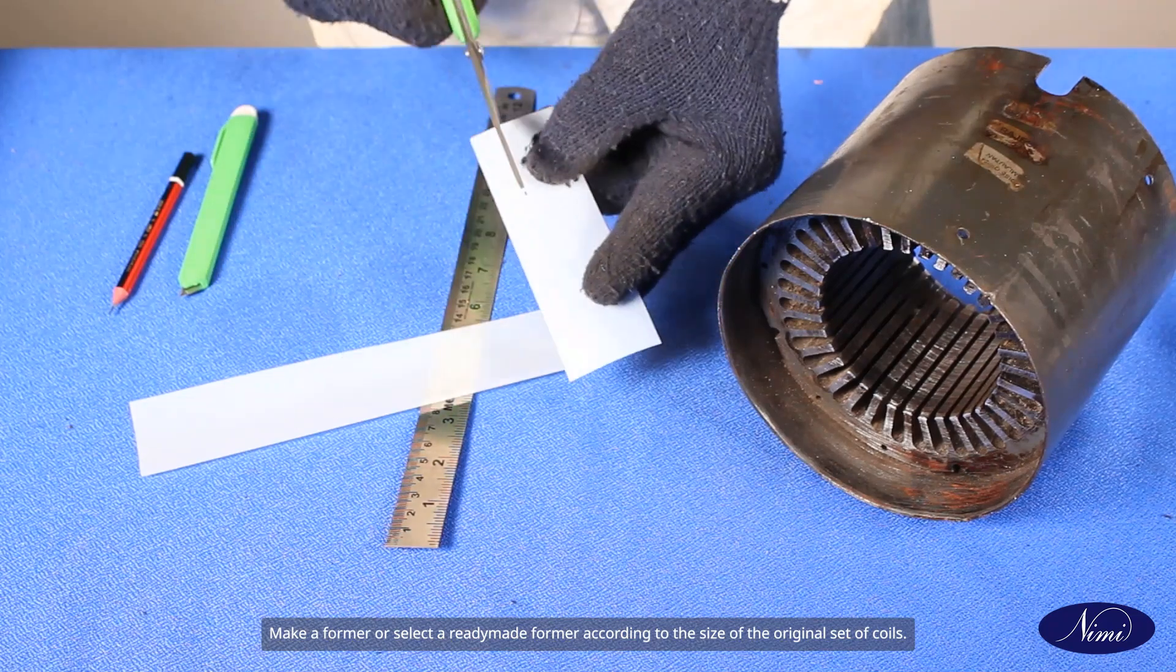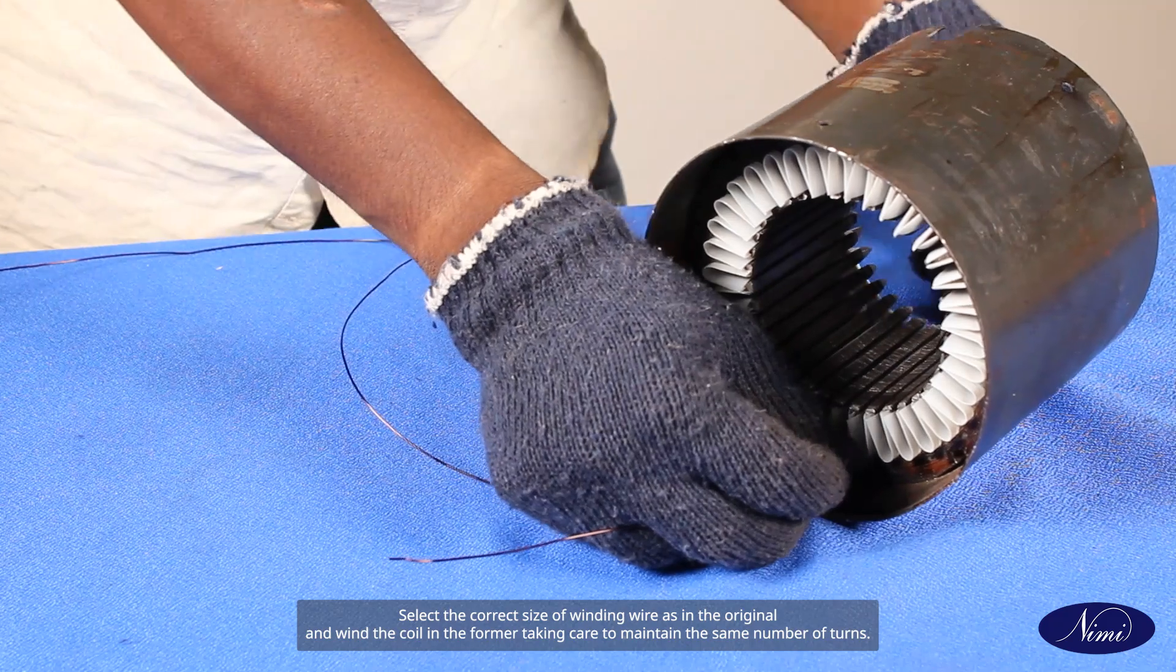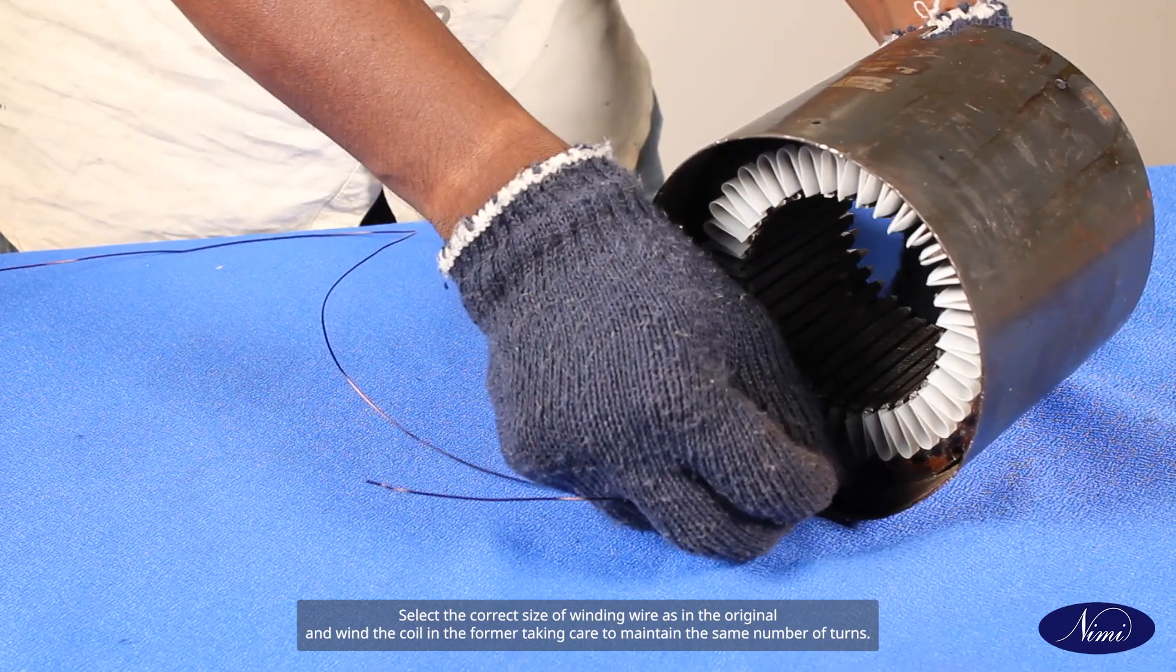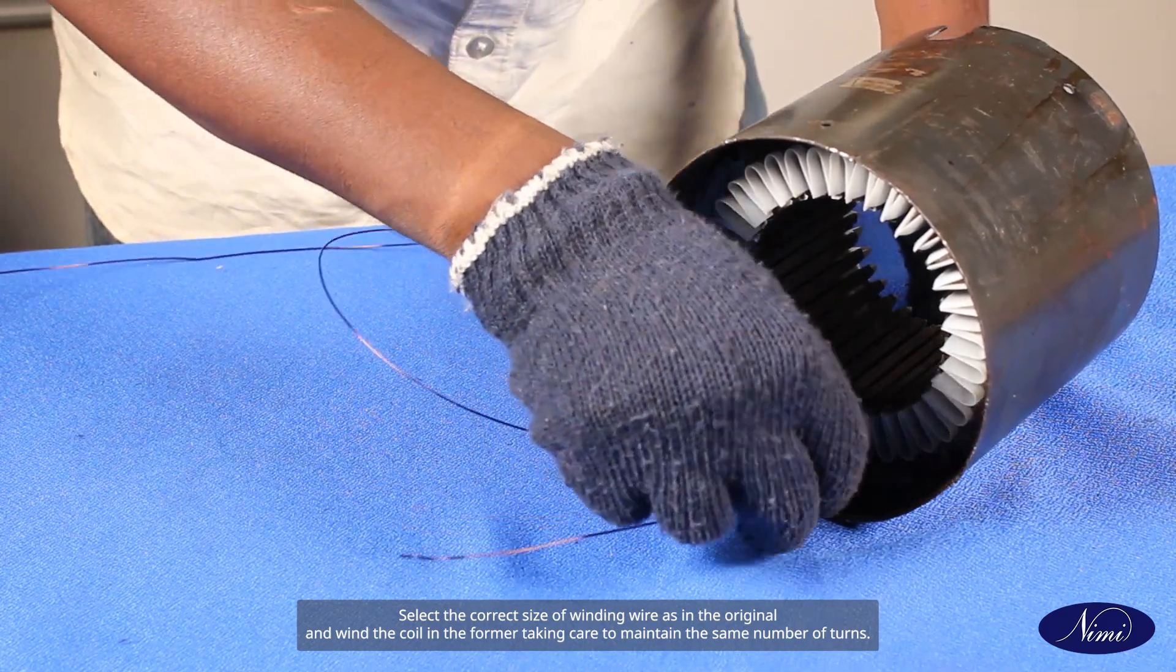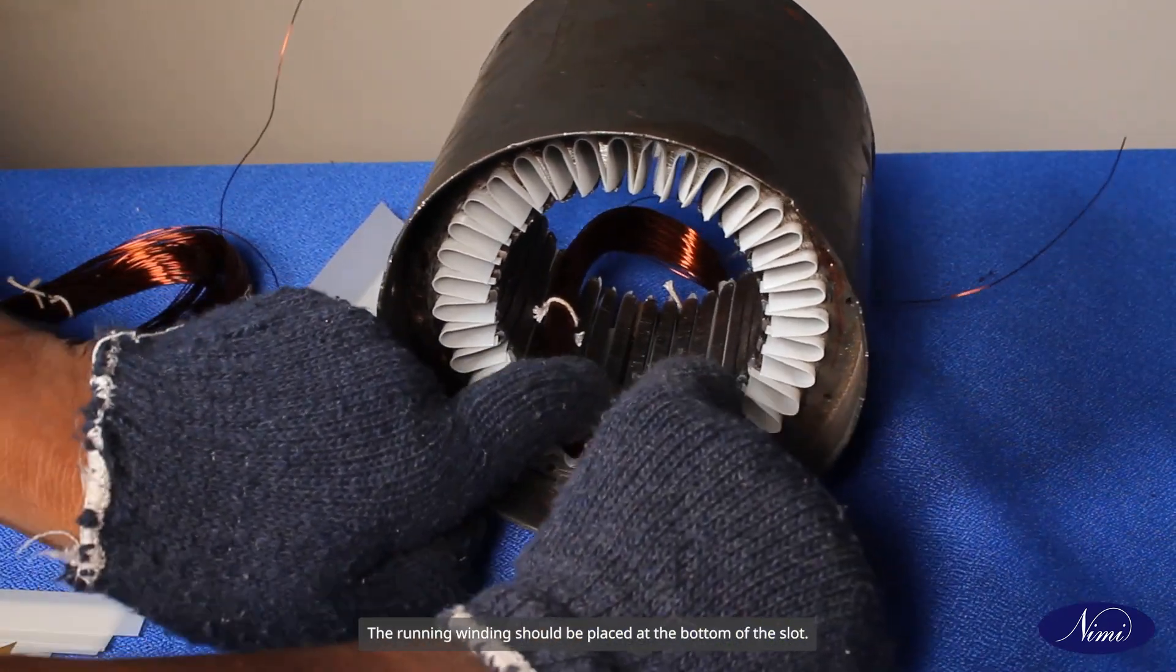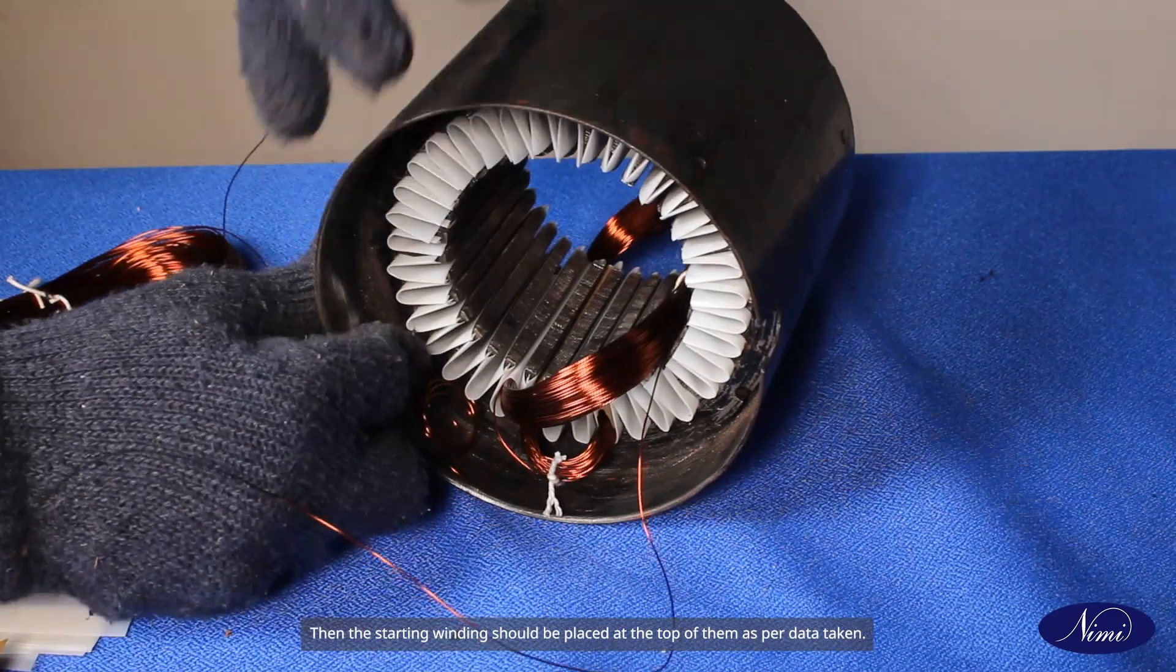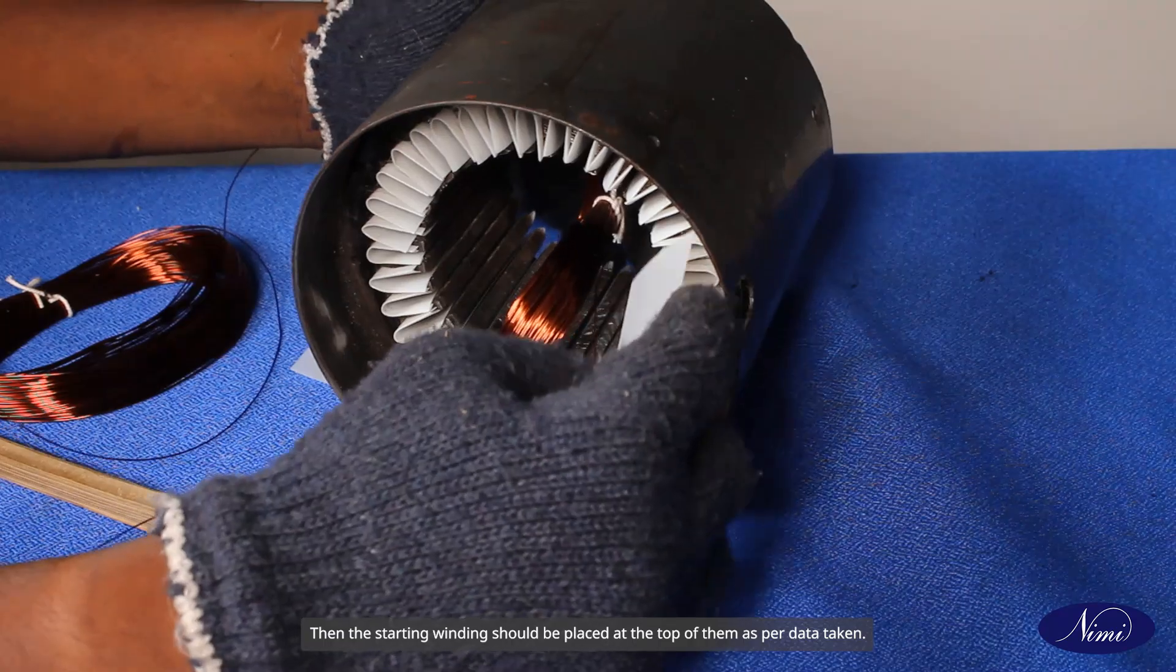Make a former or select a ready-made former according to the size of the original set of coils. Select the correct size of winding wire as in the original and wind the coil in the former, taking care to maintain the same number of turns. Make the required number of main and starting winding coils. The running winding should be placed at the bottom of the slot, then the starting winding should be placed at the top of them as per data taken.